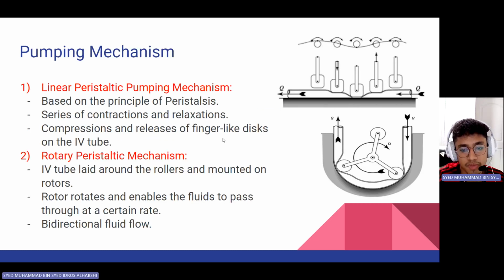Secondly, let's talk about the pumping mechanism. There are two types: the linear peristaltic pumping mechanism and the rotary peristaltic pumping mechanism. For the linear peristaltic pumping mechanism, it works as a series of contractions and relaxations, similar to our digestive system. The IV tube is placed against the tubing guide, and finger-like discs compress and release the IV tube sequentially, allowing fluid to flow at a certain rate in a ripple or wave-like motion through the tube, as seen in the top photo on the right.